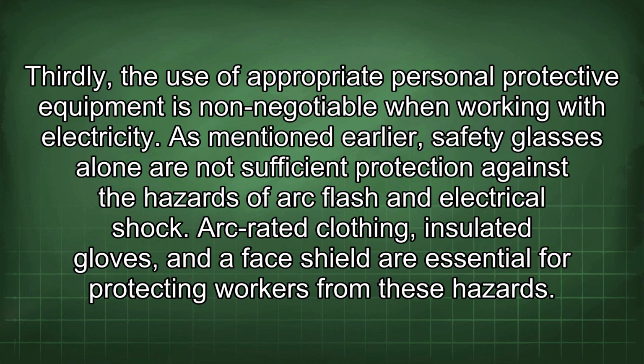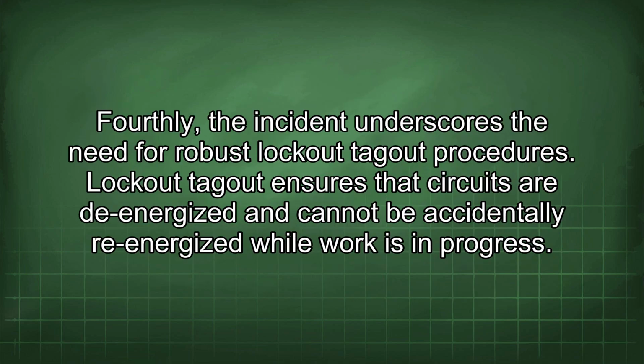Thirdly, the use of appropriate personal protective equipment is non-negotiable when working with electricity. As mentioned earlier, safety glasses alone are not sufficient protection against the hazards of arc flash and electrical shock. Arc-rated clothing, insulated gloves, and a face shield are essential for protecting workers from these hazards. Fourthly, the incident underscores the need for robust lockout-tagout procedures. Lockout-tagout ensures that circuits are de-energized and cannot be accidentally re-energized while work is in progress.